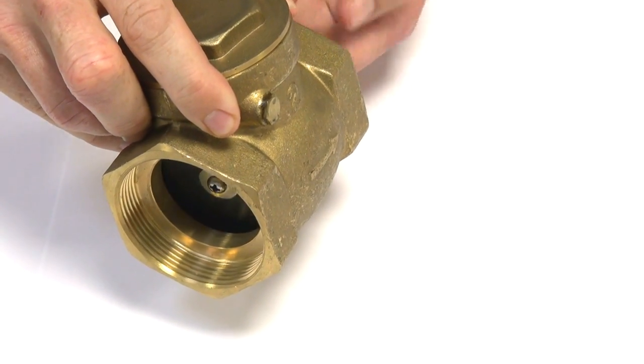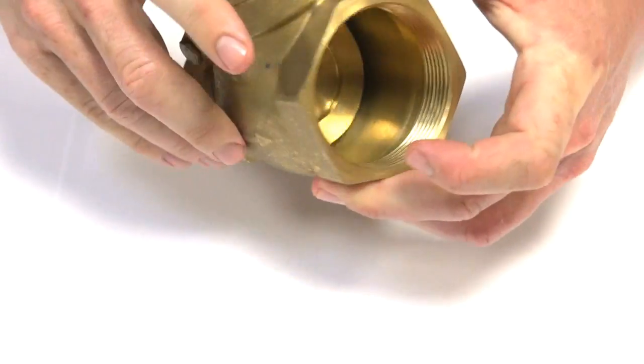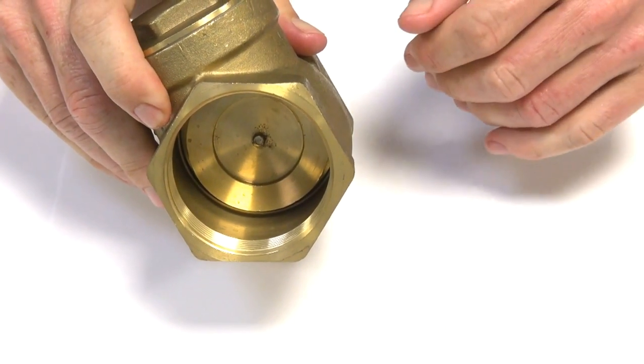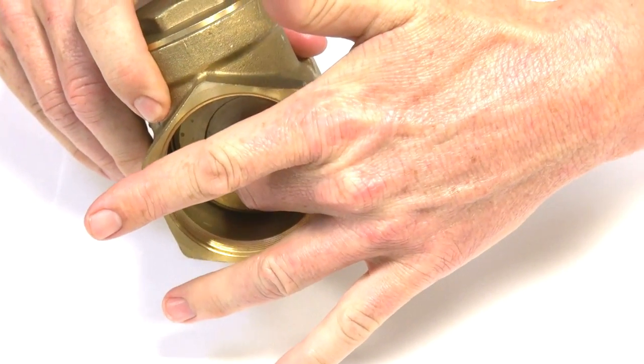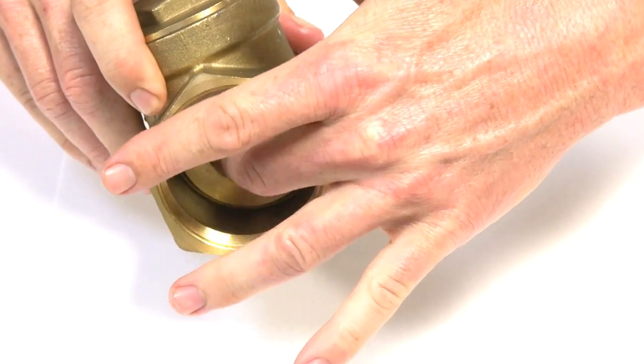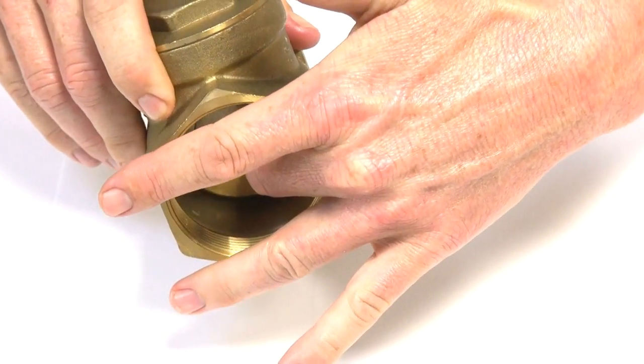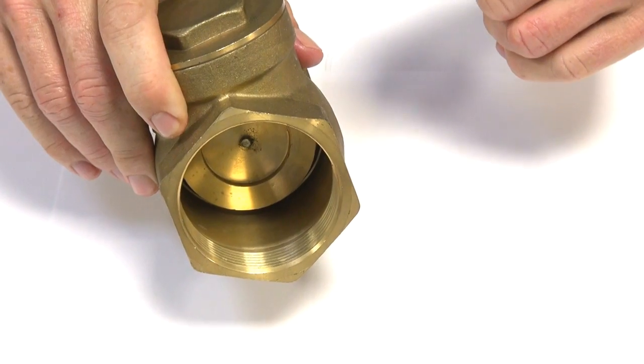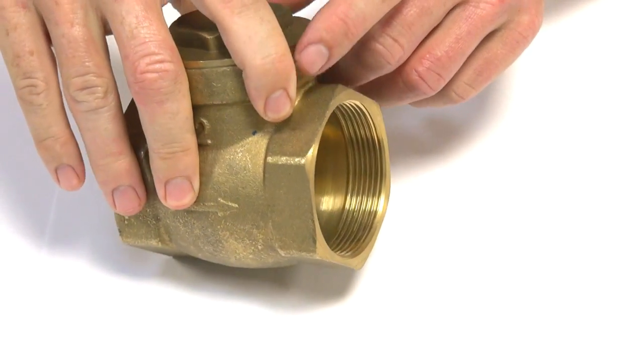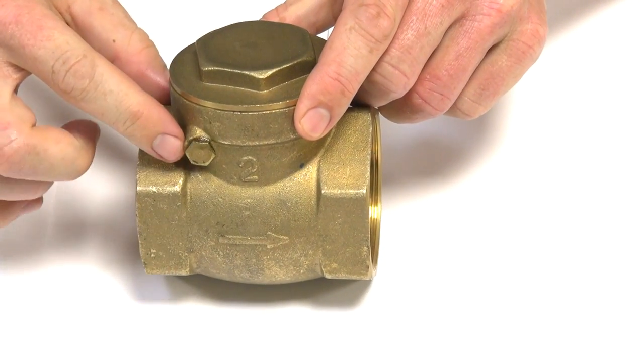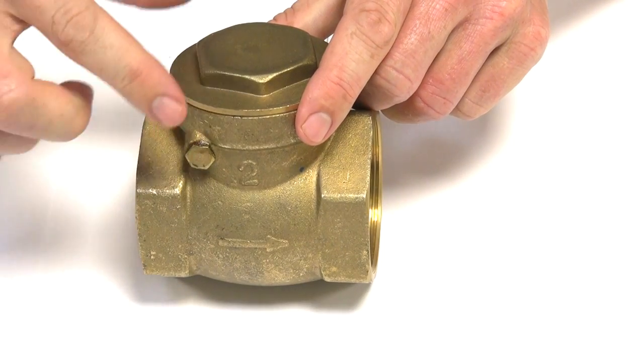When the fluid, air, or inert gas comes in the other direction, it pushes against the back of the gate here and pushes that into the seat and stops any flow going through. So it's used as a check valve. You can see this part here, this is where the gate is hung and where it swings.